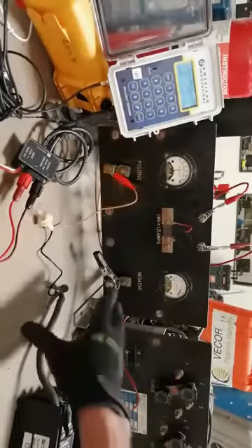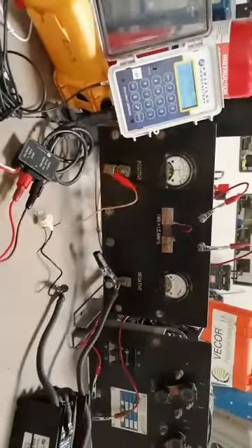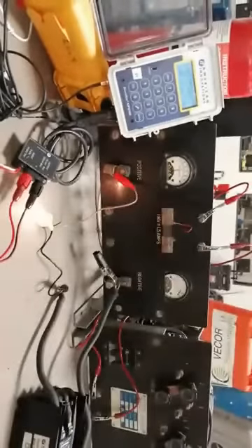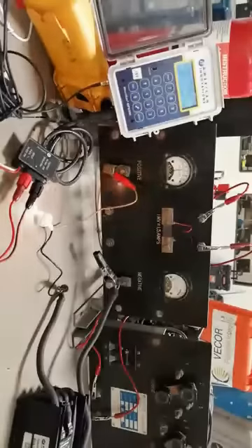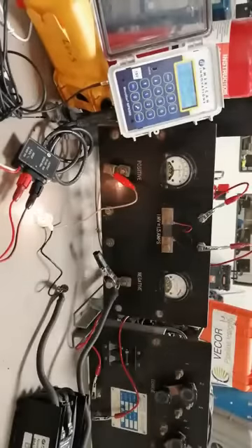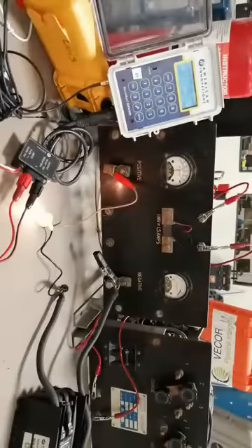I'm doing it with a negative wire, but I can also do it with a positive wire. It doesn't matter which one I use. This is useful for making instant off potential measurements for CIS, with potential measurements over short intervals, and even for DCVG, which is used in much shorter cycles, like 0.7 seconds off and 0.3 seconds on. This is how to interrupt the system.